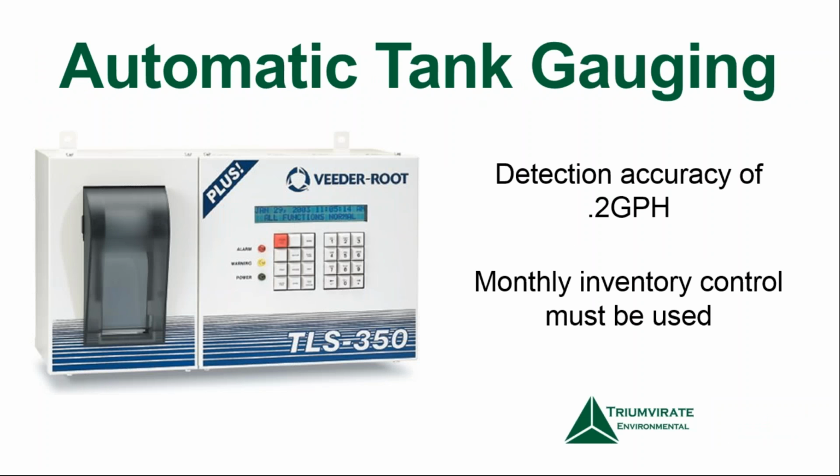This next slide just shows what a Veeder-Root system is. So if you're walking through a facility, you don't know that you have a UST, and you see a Veeder-Root on the wall, ask the question as to what it reads to, because this will be reading from an underground storage tank, and it's going to give you an accuracy of 0.2 gallons per hour of what's inside your tank. And this is going to allow for monthly inventory control, and it allows you to see what is in your tank at any given time. There's also a printout, and it'll give you everything that's in there.